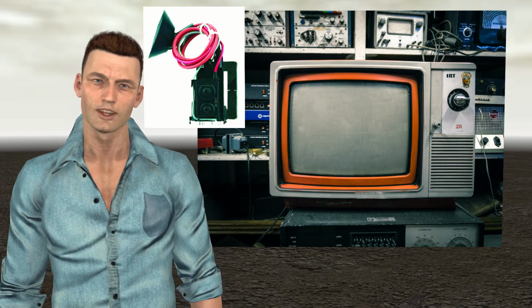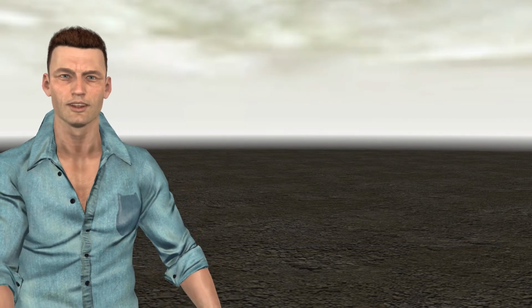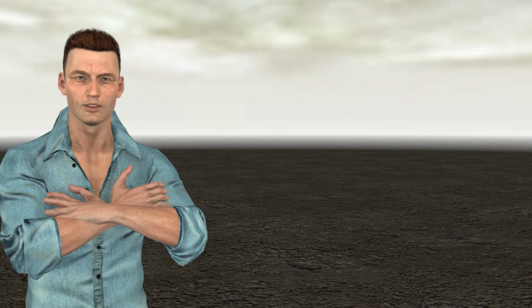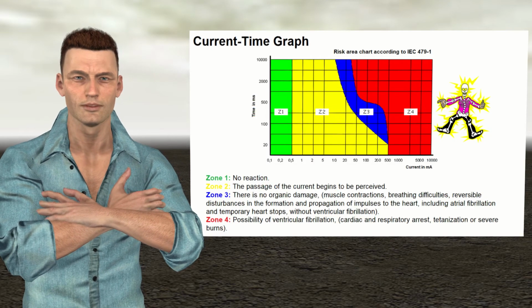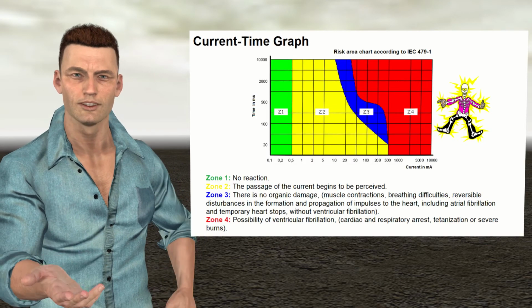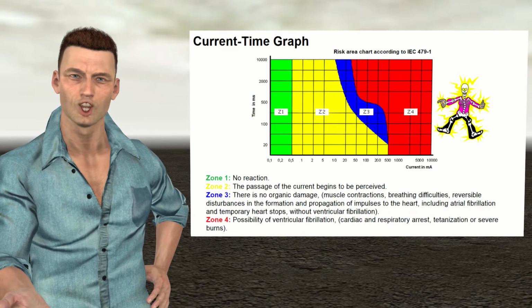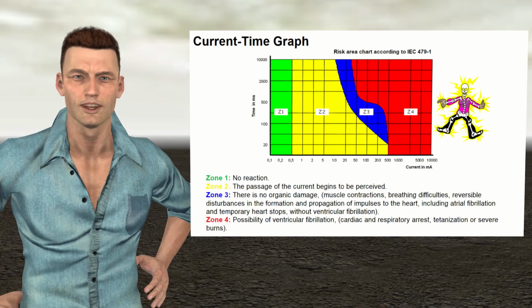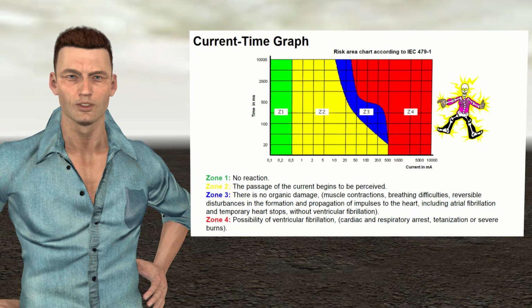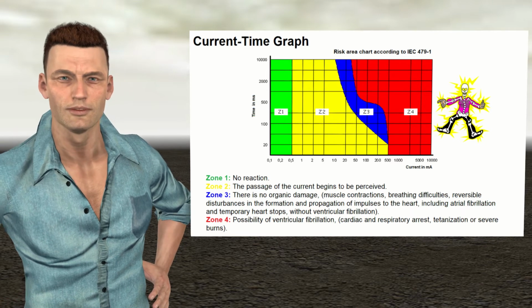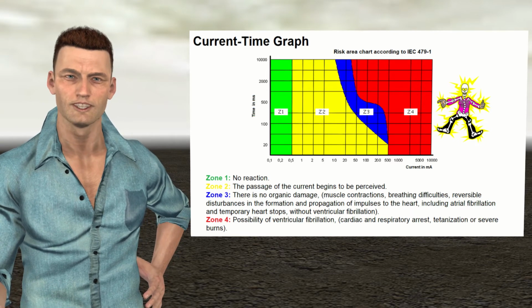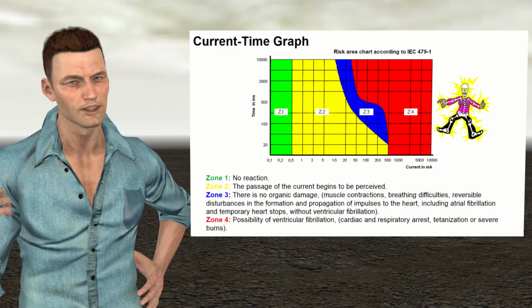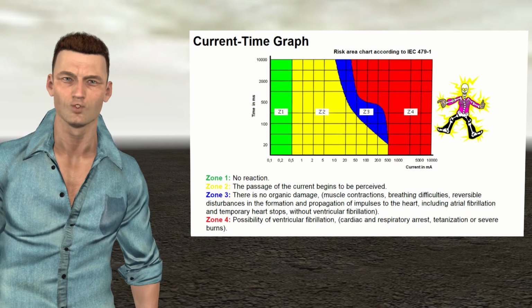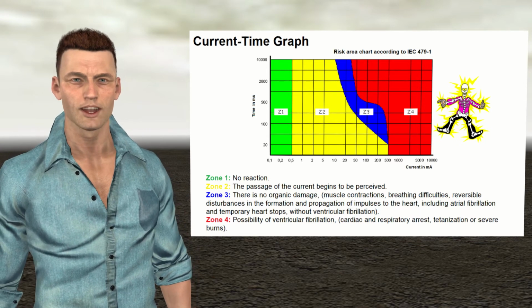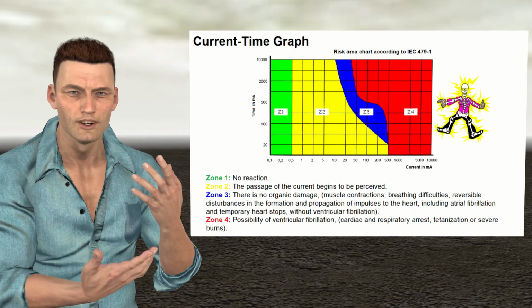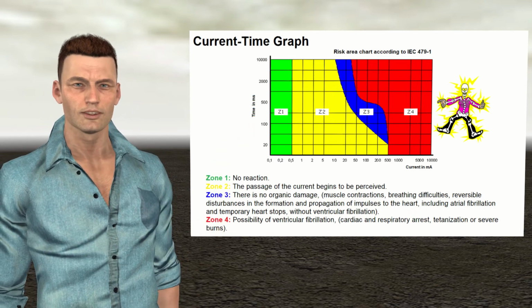In these applications, a direct discharge, despite being unpleasant, should not normally pose a risk to the technician's health. As we see in the chart of time versus current risk zones according to the standard IEC 479-1, for a couple of milliamps we would be in a safe zone for most people. On the contrary, this type of probe is not designed to be used in medium voltage electrical distribution systems, in which an electrical discharge would have fatal consequences for the technician as there is no current limitation to protect it.